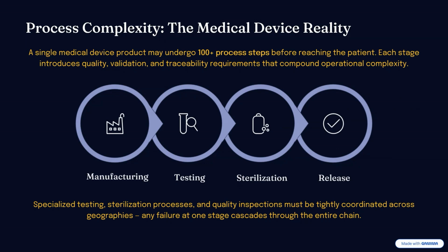Similarly, sterilization, that is the key point. We have recently been facing issues in sterilization when we say, oh, we have sterilized it. It has been sterilized, but this is not a standard sterilization for our product. In the case of ETO sterilization, you need to have a safety margin. You sterilize it, and it should be degassed before it moves to patients.